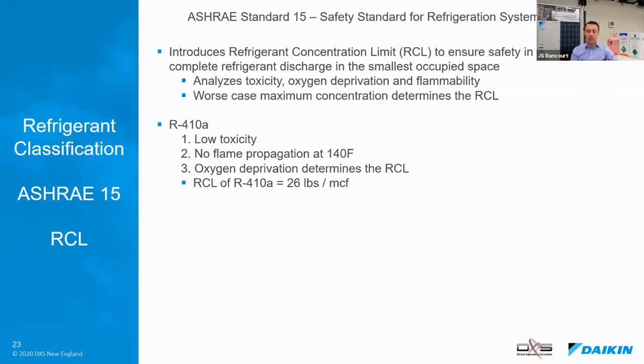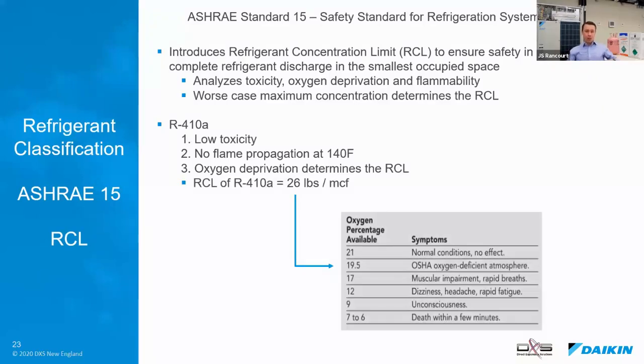What that means for reference is, if ever a room was at that limit, with 26 pounds per 1,000 cubic feet of concentration of R410A in a room, that is the equivalent of OSHA's minimum oxygen amount for a healthy environment. For comparison, in terms of altitude, that's about the same as being at 2,000 feet of altitude. It's not going to kill you, although if you start to have twice the limit of refrigerant, you start to be at 5,000 feet, 8,000 feet, you have three times the limit. Now it's getting similar to being at 15,000 feet and up in the big, big mountains. And eventually, if you were to be up there for an extended period of time, you start to have some issues, as shown by this OSHA table here.